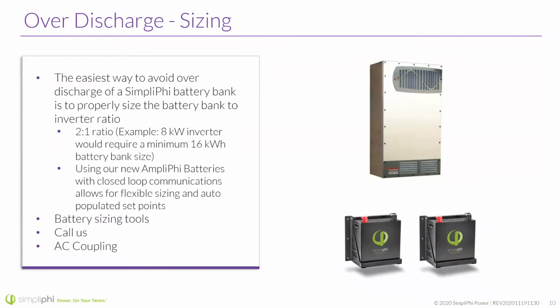So the ratio is the easiest way. You can't go wrong. If the inverter is sized correctly and the battery bank is sized correctly to that inverter, you will not have over discharge. It's the safest bet. We can use our AmpliPhi battery. The AmpliPhi has closed loop communication, which actually allows for flexible sizing and automatically populated set points. It basically acts as the brain and can tell inverters that it communicates with not to over discharge. But if you're using the standard Phi battery, I always recommend sticking to this ratio. You won't have any issues there and you won't run up to over discharge.